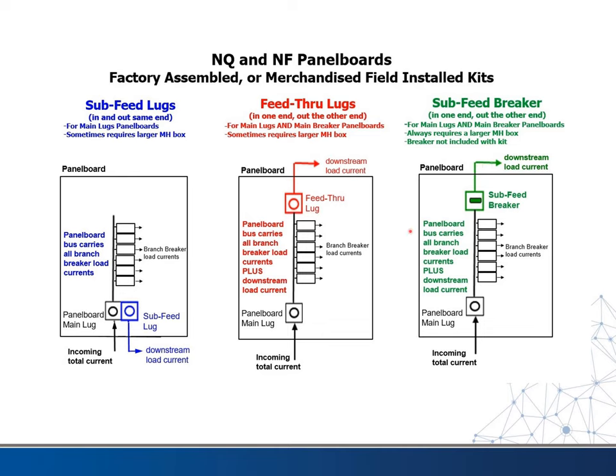So this could be like a 225 amp panel, but we want to add a smaller 100 amp panel just to give us a few more breakers. So we'd put a 100 amp breaker and 100 amp feeder going over to that. So here's a diagrammatic look at the three scenarios we just talked about: sub-feed lugs, feed-through lugs, and sub-feed breaker.